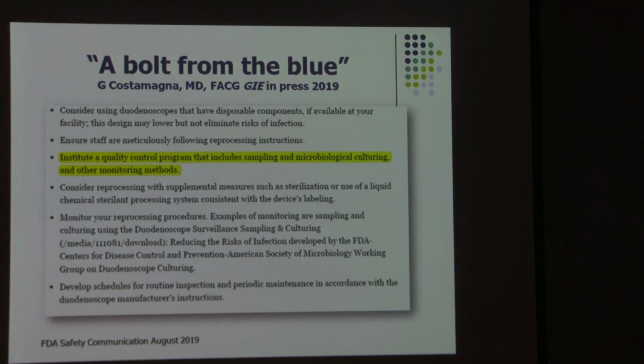You mentioned that double cleaning does not really help, but that manual cleaning in between would. Would you recommend that? This is something that has to be considered. Here's where we are right now. Supplemental measures are still recommended, and double high-level disinfection is still recommended by the FDA. The way I always see it, if you don't know what to do, follow the law. So the FDA is our law. As of April 2019, that is what it recommends. However, they don't make it easy for us because they don't specify what double high-level disinfection means.